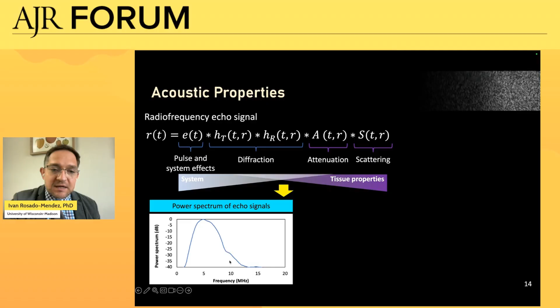To briefly show you how we can extract some of this information, usually the scanner computes the power spectrum of the echo signals, that is the distribution of the energy of the echo signals as a function of frequency. After some signal processing and mathematical approaches, we can extract a quantitative feature, which is the attenuation coefficient, which is a measurement of the loss of energy as the pulse travels through the tissue due to absorption and scattering. And once we know the attenuation, we can also extract a second quantitative feature, which is the backscatter coefficient, which is a measurement, an absolute measurement, of the reflectivity of tissue.